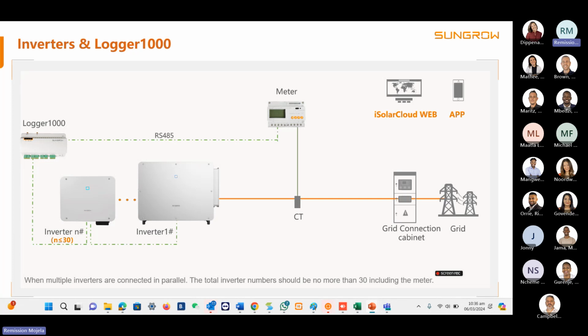But remember, all the comms will directly go to the Logger 1000, which has 3 COM ports available. It has A1B1, A2B2, and A3B3, which are completely separate RS485 ports. So the inverters will go on to their own port. The meter will go to its own port as well, separately. So now the Logger will be the master of the whole installation.